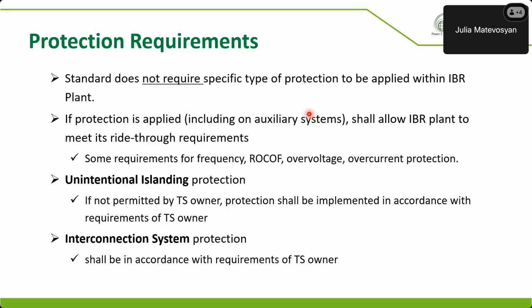If protection is applied, it shall allow the IBR plant to meet its ride-through requirements. We did spell out a little bit of detail for voltage, frequency, ROCOF, and overcurrent protection, and I will show you that in the next few slides. Unintentional islanding: if not permitted by the transmission system, then protection shall be implemented in accordance with the requirements of the TS owner. So most transmission entities out there would like some sort of anti-islanding protection.